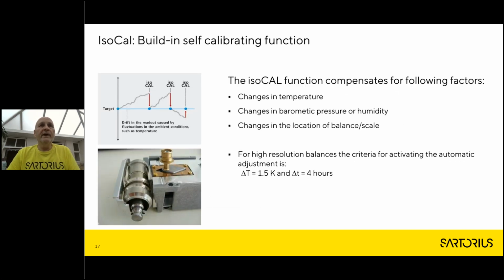Let's talk a little bit more about the ISOCAL function in Sartorius balances. ISOCAL compensates for changes in temperature, in barometric pressure or humidity, and also changes in the location of the balance, as we've just talked about. On high resolution balances, the activation criterion for automatic adjustment is 1.5 degrees Celsius or Kelvin, or at 4-hour intervals. The balance should automatically recalibrate itself and adjust the slope.